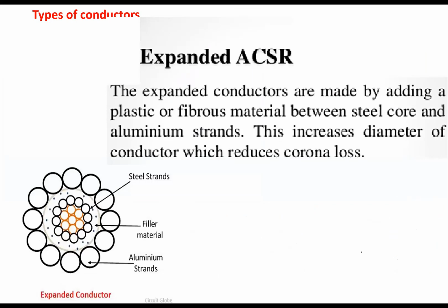So these are normal ACSR conductors only, but between one layer of strands and other layer of strands, we are filling with some filler material like jute, paper, or any fibrous material, so that we are increasing the overall diameter, the overall size of the conductor.